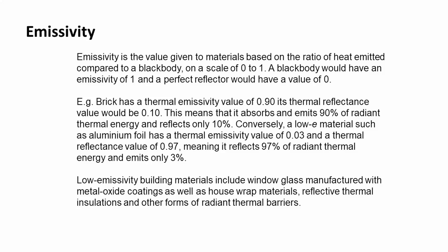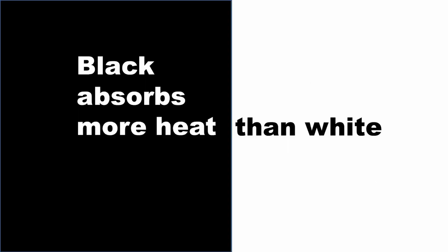There are a couple of terms that need explaining. Emissivity can be thought of simply as the difference between black and white. It's the value given to materials based on the ratio of heat emitted compared to a black body, on a scale of 0 to 1. A perfect black surface would have an emissivity of 1 and a perfect reflector a value of 0. In construction, materials like brick don't reflect, while materials such as aluminium foil do reflect. Low-E materials make our construction more efficient.